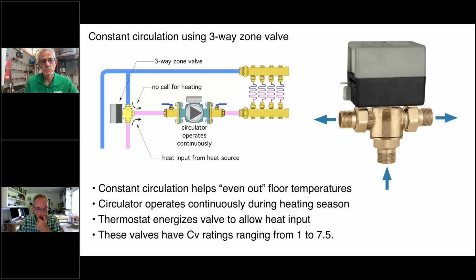You need a three-way ball valve. It's the same concept as shown here. It's just a valve body that has a higher CV rating. So in a commercial application, again, highway garages that are 12,000 square feet with maybe 2 or 3 zones in it, the CV isn't quite large enough. But in residential or light commercial applications, as long as you respect the CV ratings on these valves, you'll be fine.